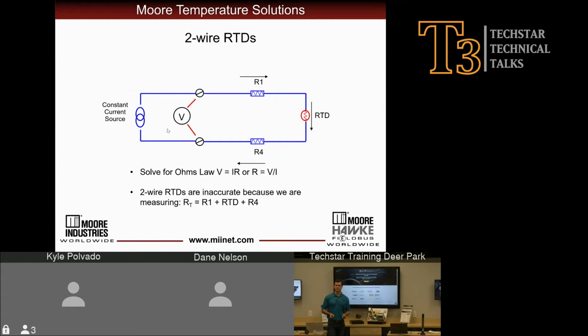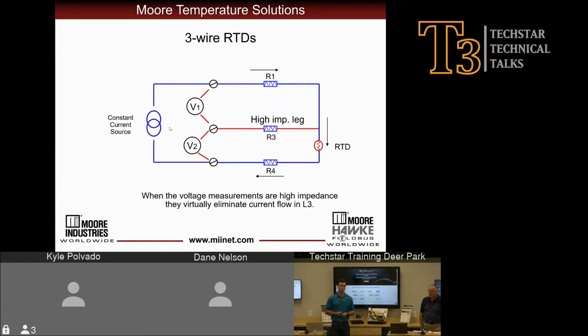So with the 2-wire RTD, you can see that we actually are including this lead leg here, R1, and this returning lead leg, R4. Now, since we're trying to measure a resistance in an RTD element, and we include the lead leg and the returning lead leg, R1 and R4, our temperature measurement's not very accurate. We're including additional resistance into our RTD calculation of what a resistance means in terms of temperature. So if we add resistance to that, by nature, our temperature is going to be higher than what we're actually measuring at our process. This led our industry to develop the 3-wire RTD.